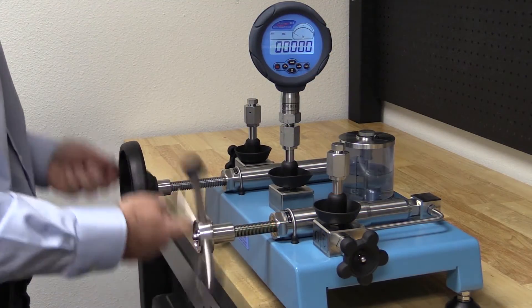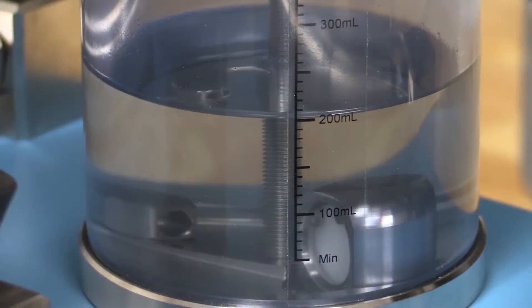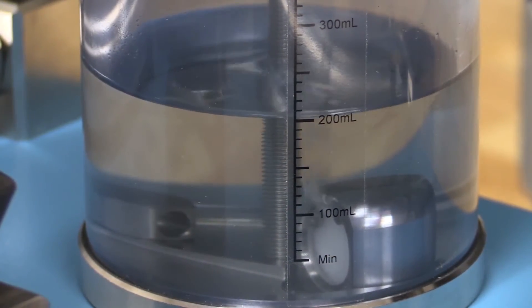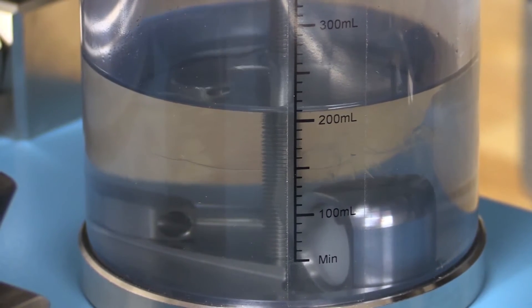Now with the vent valve left open, we will turn the two screw presses all the way in. If you have gas still in the system, you'll notice bubbles coming into the liquid reservoir as you turn in the screw presses.